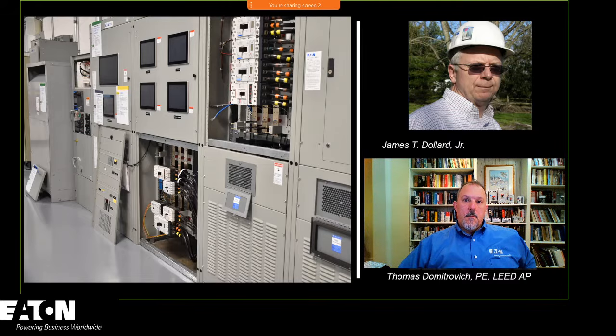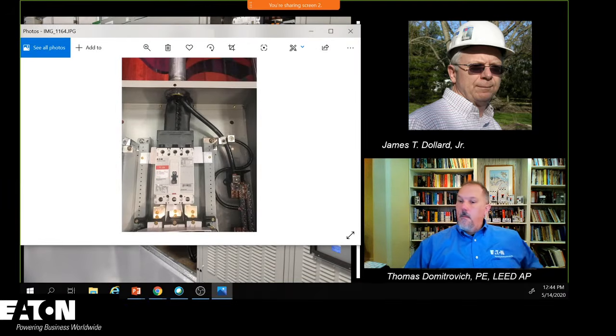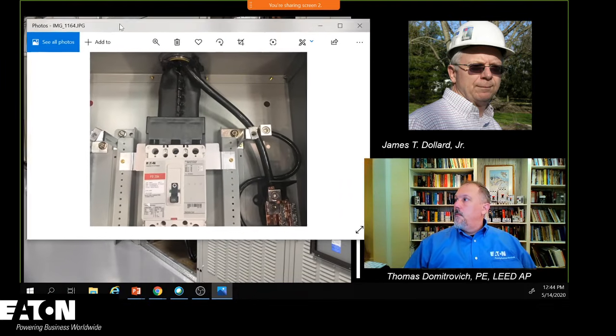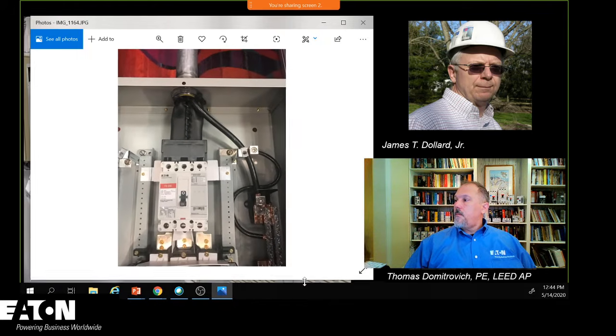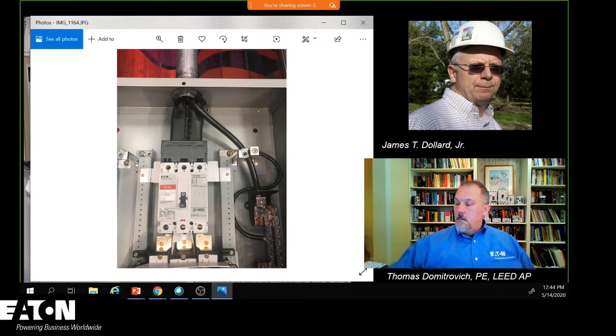Now, they don't eliminate the possibility of contact. Some of them do a superior job and may just eliminate the possibility of contact. There's an example right there. Tom just pulled that up. So if this is service equipment, we've got problems. I represent the electrical construction industry, and when it comes to NFPA 70E, we cannot go into service equipment if we're following the requirements in NFPA 70E. We've got exposed line side terminals, and there's no way we can apply the tables. If we're applying the tables, we can take a few steps and determine the available fault current, but we can't estimate the clearing time of the upstream overcurrent protective device because there isn't one.